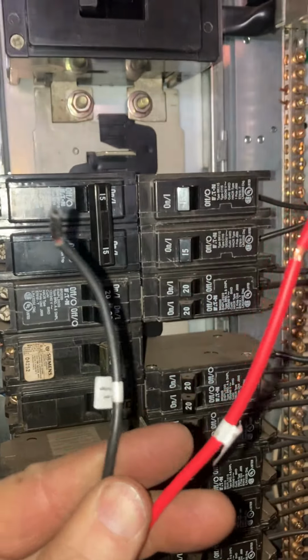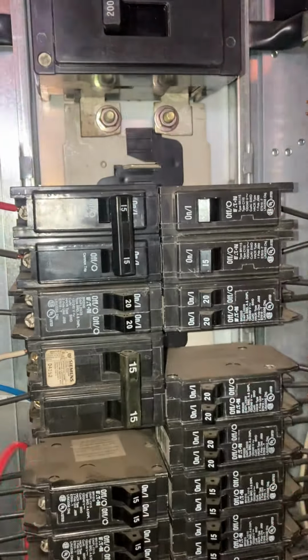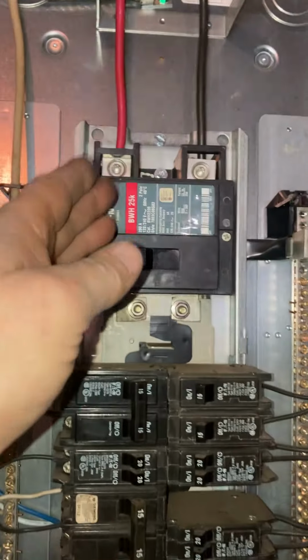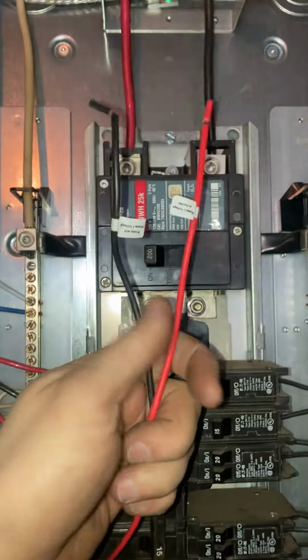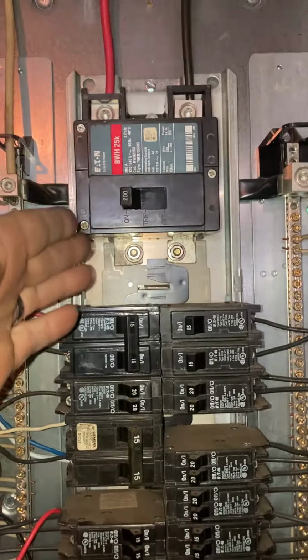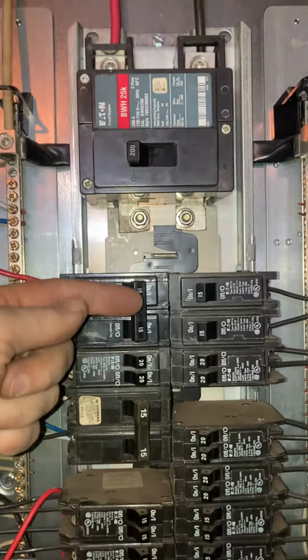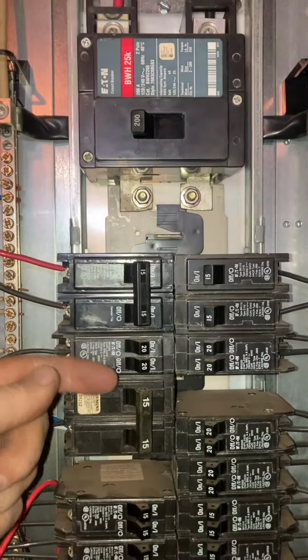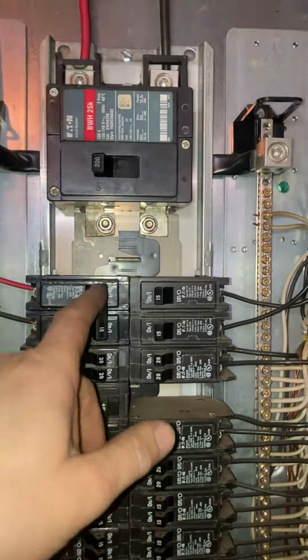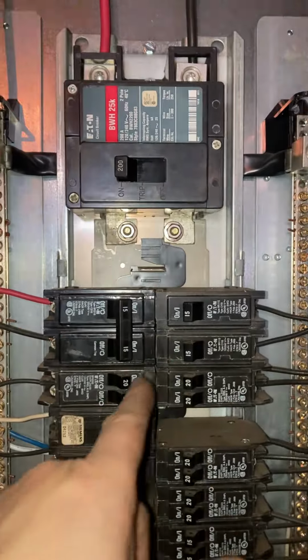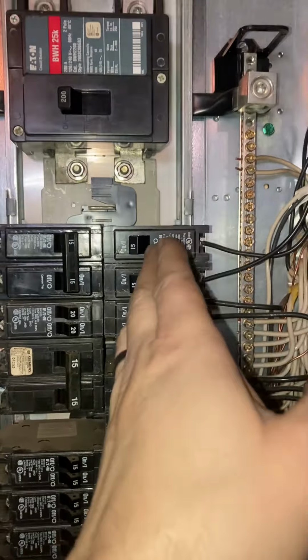Now we've got the 2 phases that we've got to hook up to alternate sides of the panel. So we've got basically the red and the black, which are going to go like that. The way electrical panels are typically configured, every other breaker gives you a different phase. You see how we've got this little S thing going in the background? There's little fingers in here, and the breakers click into those fingers.